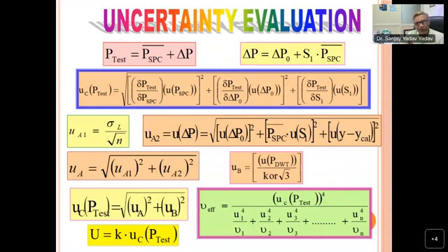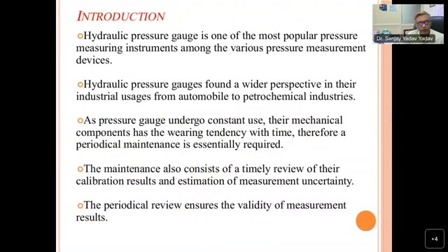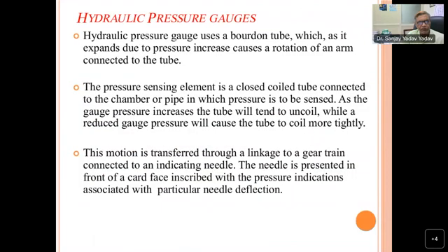When you are calibrating deadweight tester to deadweight tester, you have to make a model equation. Test gauge is equal to mean pressure on the standard deadweight tester plus delta P, which is the error. When you differentiate this equation, you can find this equation, and using this sensitivity coefficient, you can determine the exact uncertainty value of this equation. And for the linear fitting equation, I have already explained in the previous slide. This is not so important. Hydraulic pressure gauge. Okay.